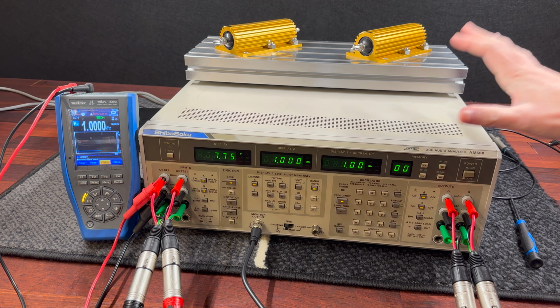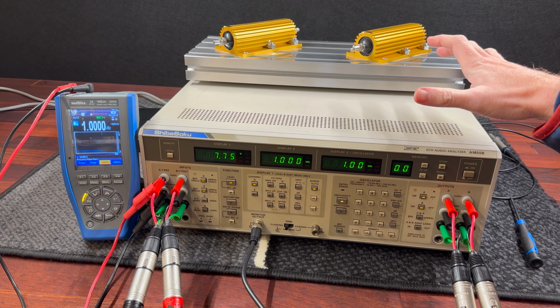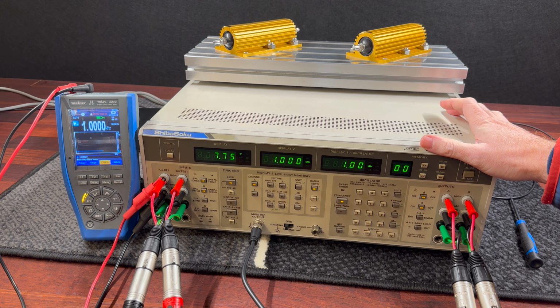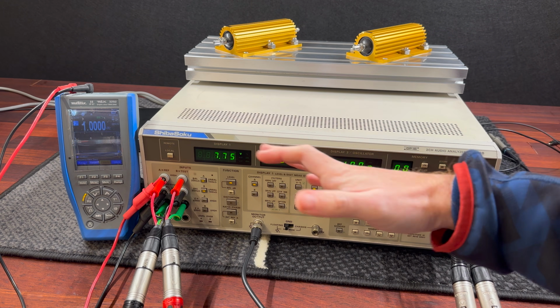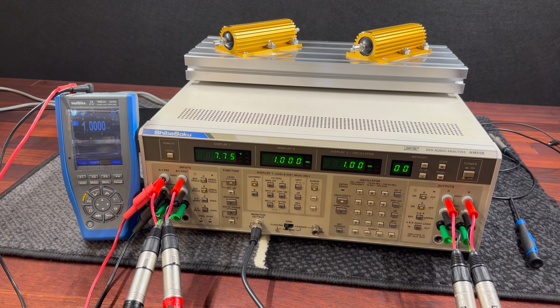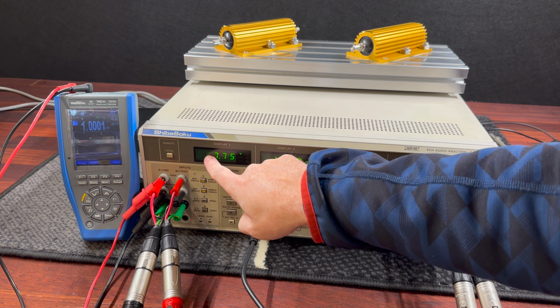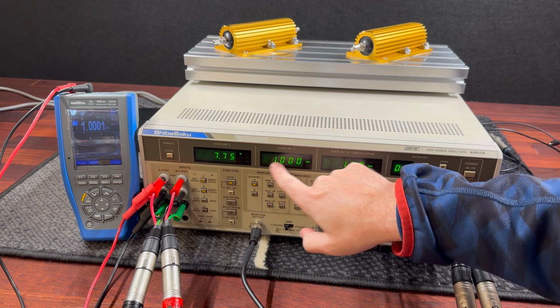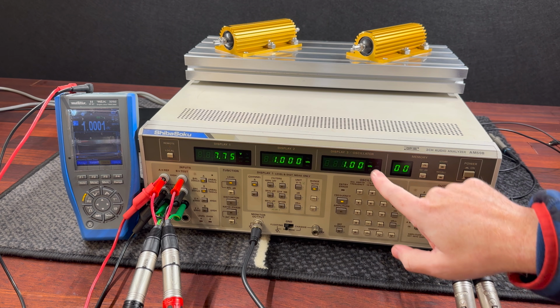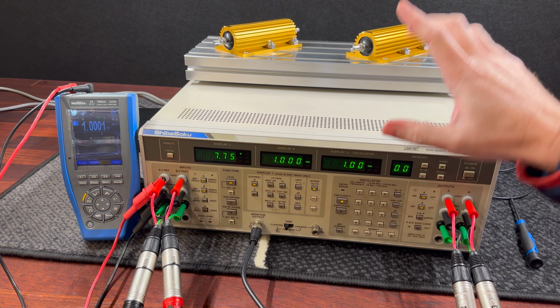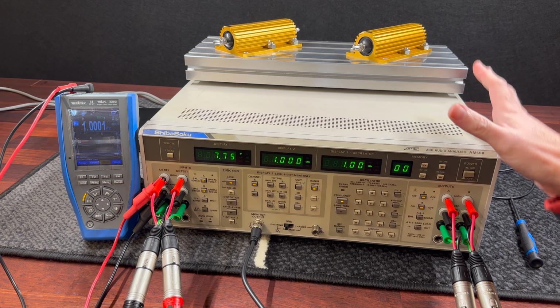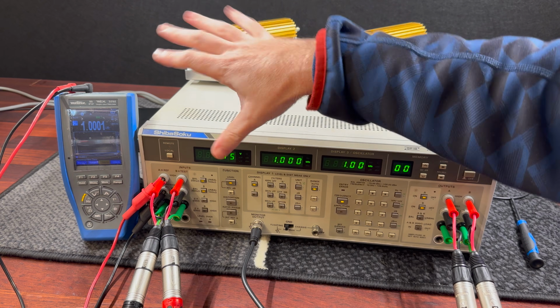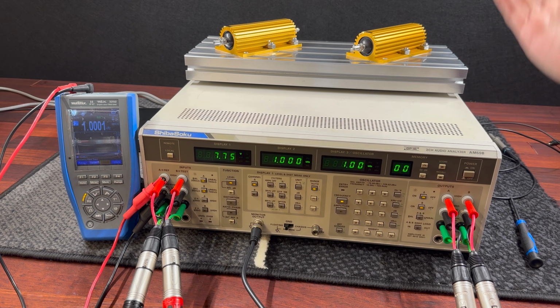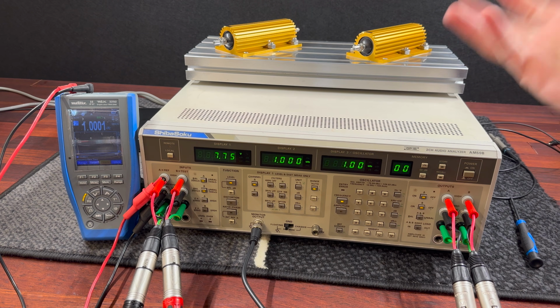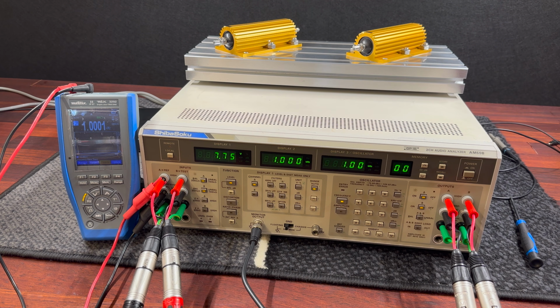Now, to do the calibration on this, I started with the output oscillator section because we needed to use the oscillator as a reference for calibrating the input side. The issue was, what am I seeing here is the voltage and the frequency. We don't know if the oscillator was right, or the voltage, or if what it was reading was right. We could have been compensating one for the other, vice versa. So we needed a known, well, better reference than the unit itself.